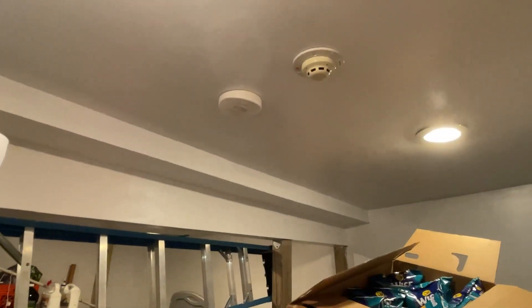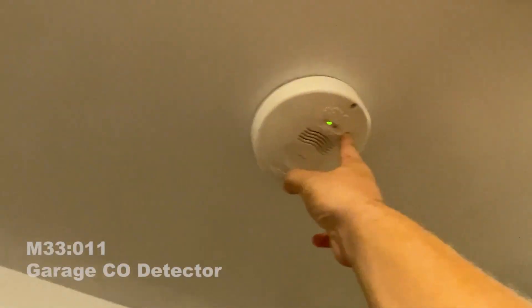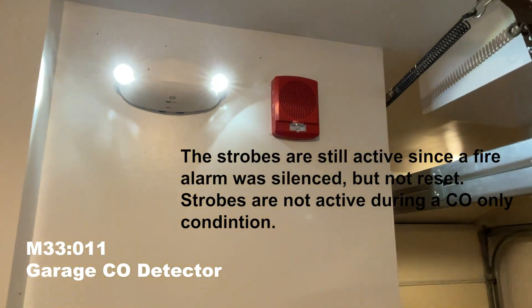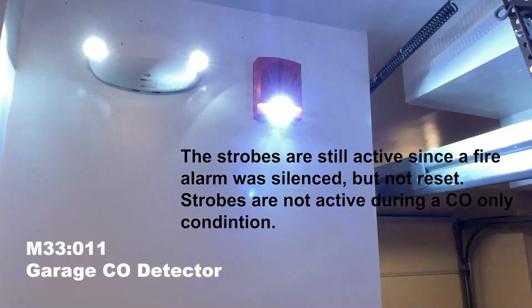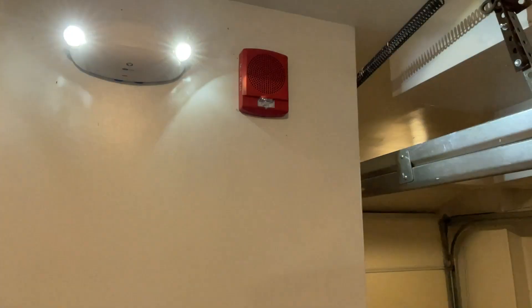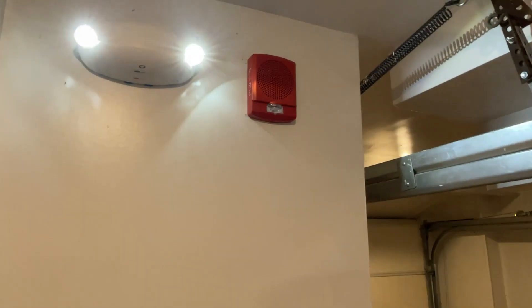We will now be demonstrating the carbon monoxide feature, which uses a different voice announcement file: 'May I have your attention please.